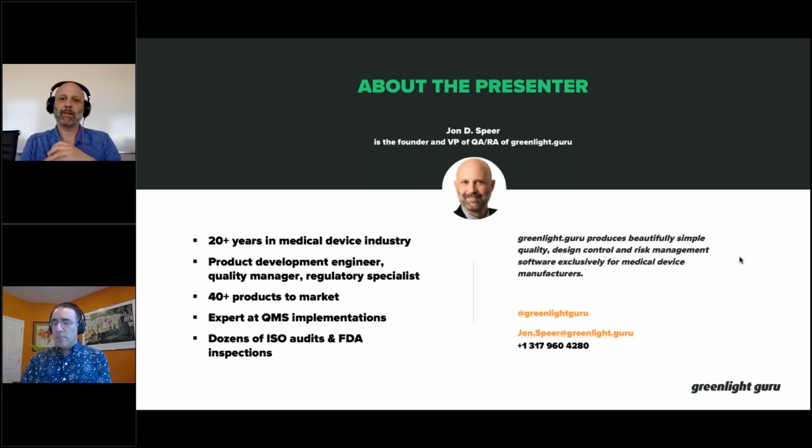And I think this is a really great example, because one thing that's important about the design and development of our product is that we need to validate the design. We need to prove that we designed the correct medical device. And part of that is to have our doctors involved in the design validation activities, provide them with simulated data that we believe to be clear, objective, and unambiguous, and confirm that they make the decisions based on that data that we would expect. So you can design a whole test or protocol around demonstrating that, and use that proof and evidence to corroborate what you identify from a probability and severity.